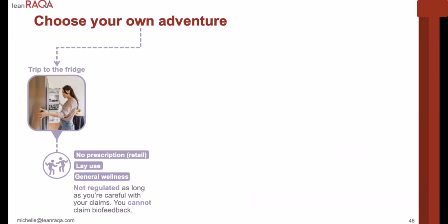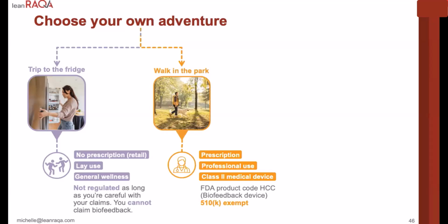If your claims, indications, intended use include it's no prescription for retail use by lay users, it could fall into general wellness. As such, it would not be regulated as long as you're careful with your claims. And then you cannot claim biofeedback. That's important, and we'll talk about that as we go here on the adventure.